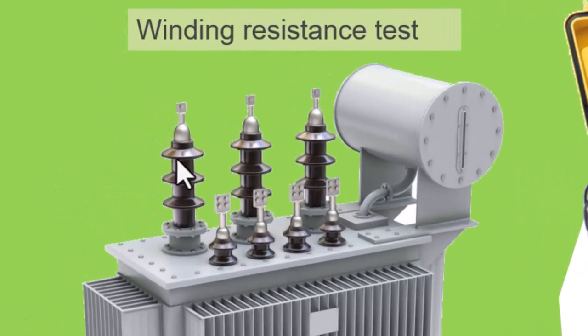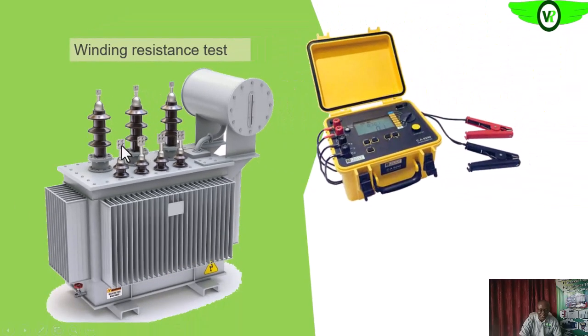So in this case, it is connected in delta, which means if you are probing between here and here is a coil, a winding, between here and here is a winding, between here and here is a winding. So this is a start point now. Between here and here is a winding, between here and here is a winding, here and here is also a winding. So when you probe this end, you are testing the winding of the first phase, between here and here the winding of the second phase, here and here the winding of the third phase. The resistance, I mean to say, not winding. If you probe between here and here, you are testing the resistance of the first phase, here and here the resistance of the second phase, and then between here and here the resistance of the third phase winding.